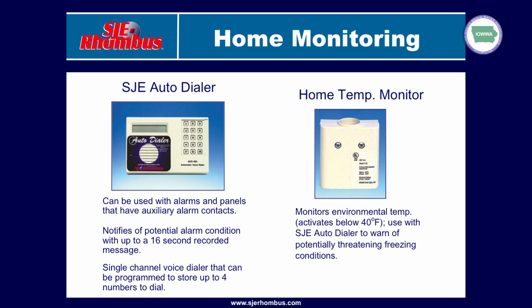Whether it's a high-level alarm or a control panel, if we have auxiliary contacts, we can also incorporate remote notification of a high-level problem or a high-level alarm with auto dialers. So I just wanted to mention that most panels, whether I made it or somebody else made it, as long as you have auxiliary alarm contacts in the panel or in the alarm, you can incorporate a dialer into the system. As long as you bring a phone line into it, you get remote notification if there's a catastrophic problem on any of your jobs.